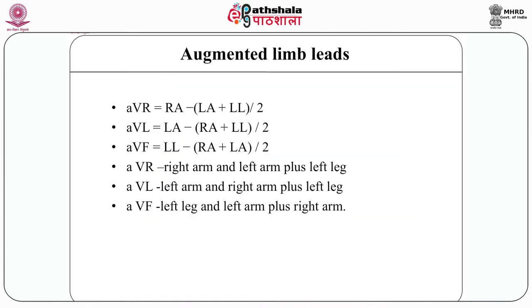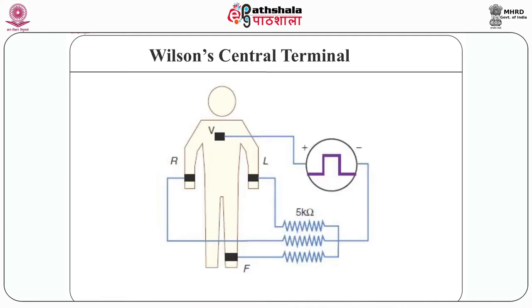Now we are going to talk about augmented limb leads. The exploring electrode forms a positive input as the right arm electrode, left arm electrode, or left leg electrode for AVR, AVL, and AVF respectively. The reference potential for the augmented lead is formed by connecting the two limb electrodes other than the exploring electrode. AVR equals right arm minus (left arm plus lower limb) divided by 2. AVL equals left arm minus (right arm plus lower limb) divided by 2. AVF equals lower limb minus (right arm plus left arm) divided by 2.